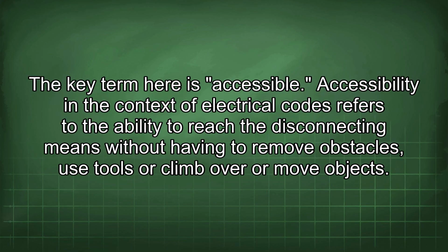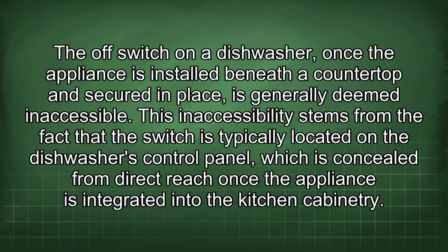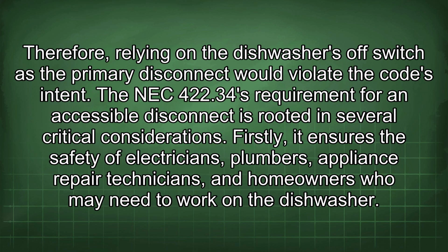The key term here is accessible. Accessibility in the context of electrical code refers to the ability to reach the disconnecting means without having to remove obstacles, use tools, or climb over or move objects. The off switch on a dishwasher, once the appliance is installed beneath a countertop and secured in place, is generally deemed inaccessible. This inaccessibility stems from the fact that the switch is typically located in the dishwasher's control panel, which is concealed from direct reach once the appliance is integrated into the kitchen cabinetry. Therefore, relying on the dishwasher's off switch as the primary disconnect would violate the code's intent.